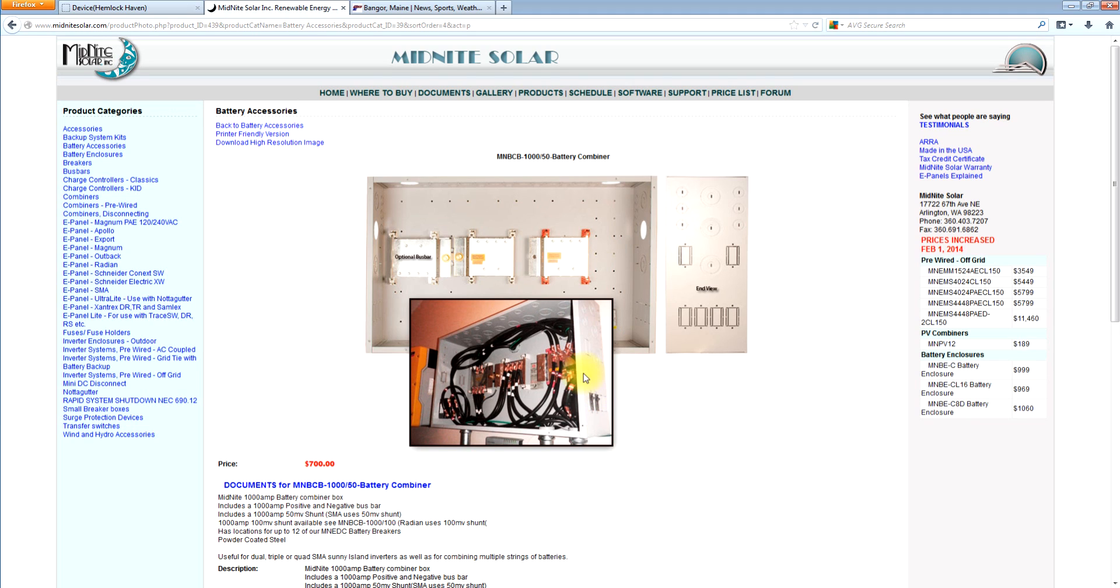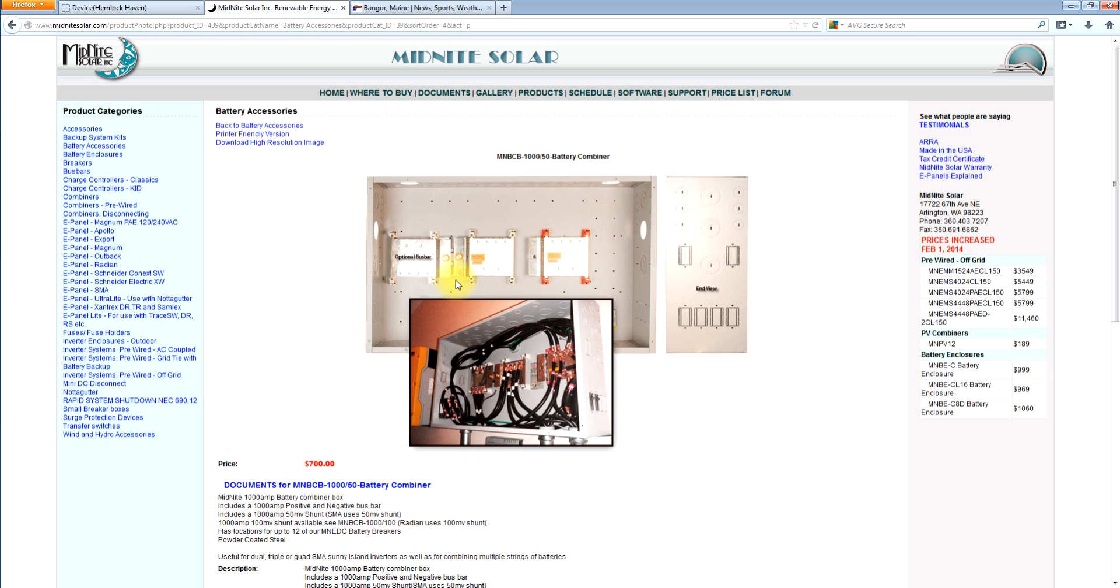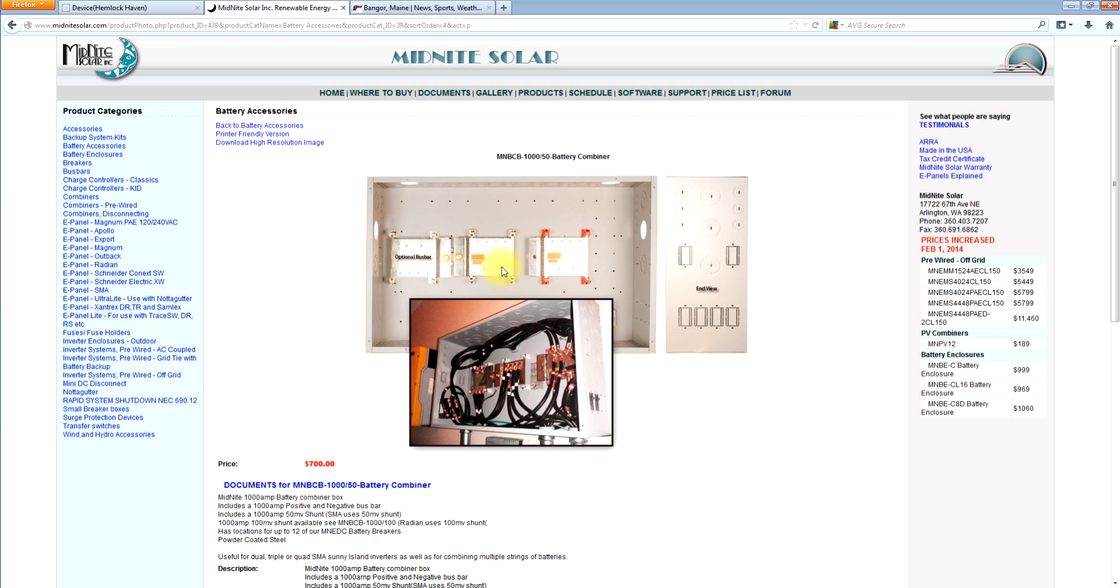So with that said, what this box does is allow you to take multiple strings of batteries out to multiple inverters, or a single string of batteries to multiple inverters, or multiple strings of batteries to a single inverter. So if you're doing both, let's say you've got four strings of batteries and four Sunny Island inverters, you can get this optional negative bus bar that goes on the other side of the shunt. So you have extra attachment points. You could bring six or twelve strings of batteries in and go out to six or twelve inverters.